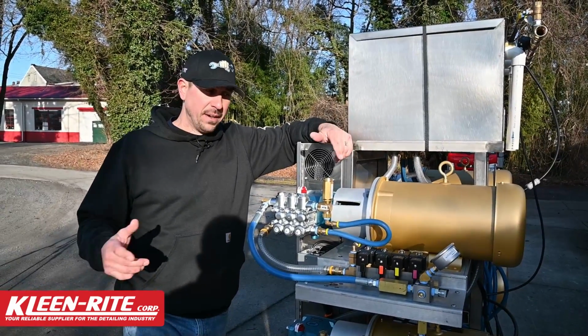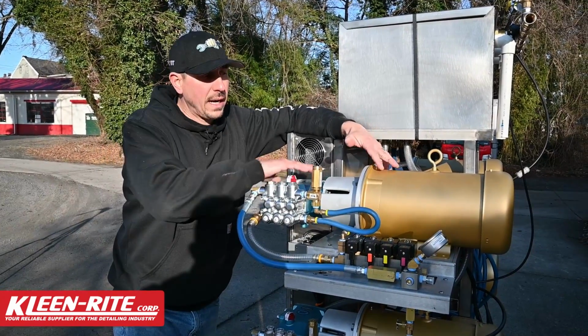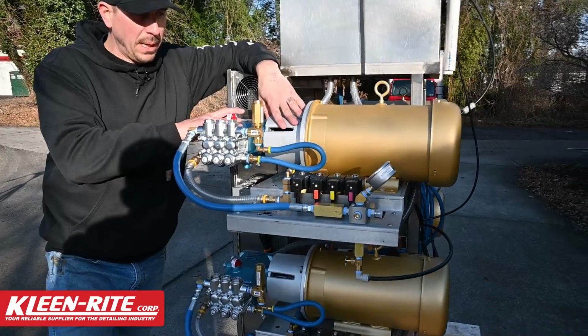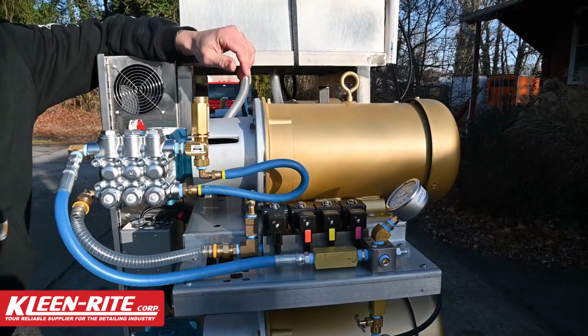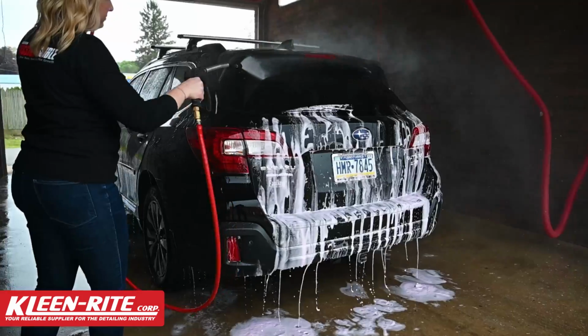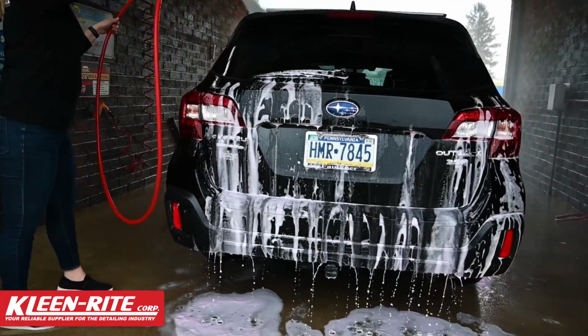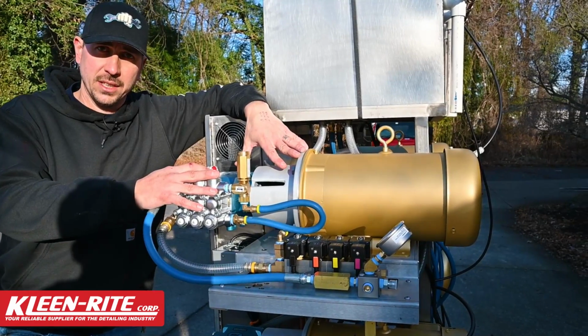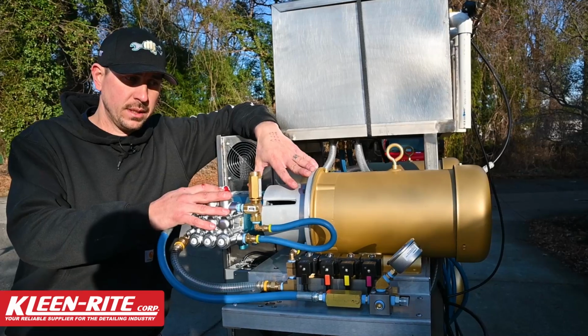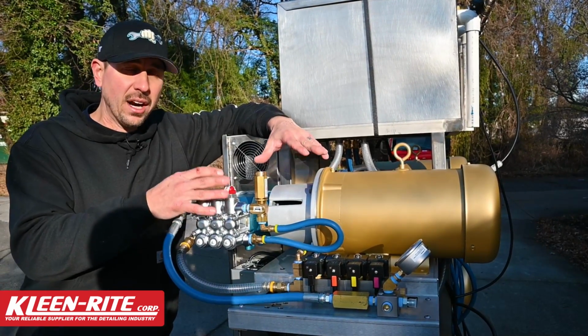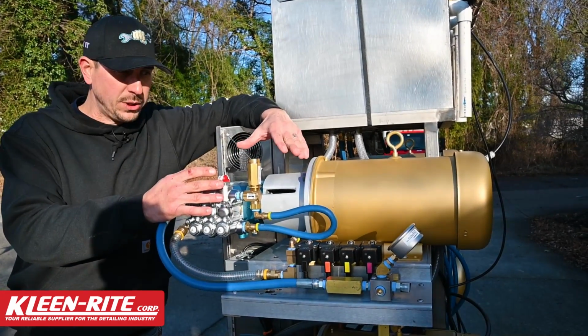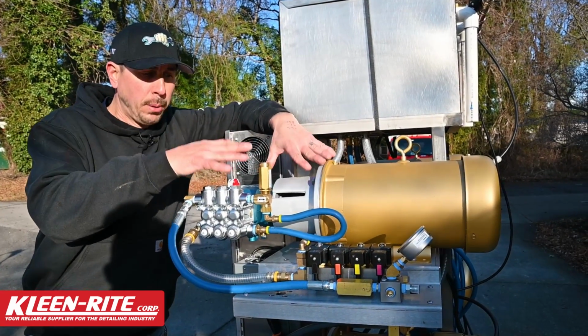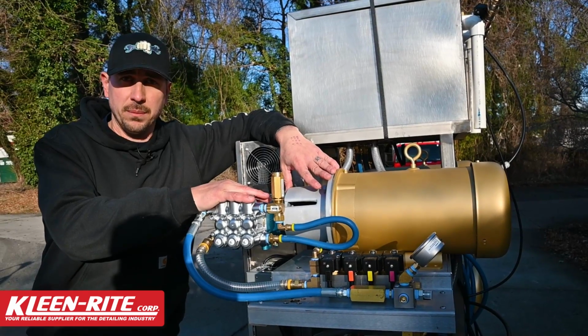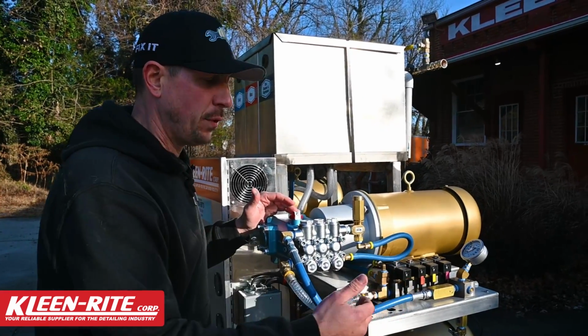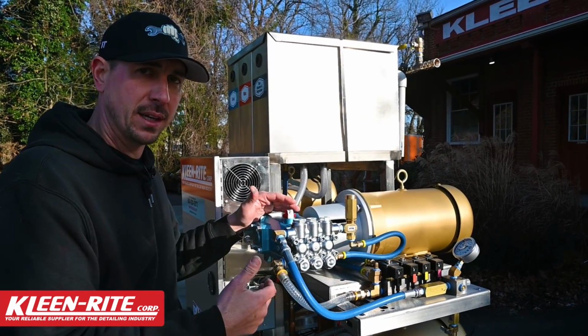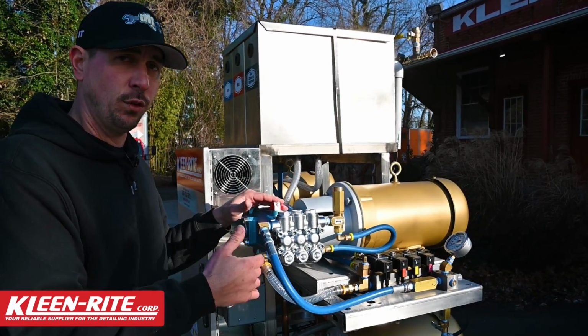So along with the VFD benefits on ease on the motor, we've also gone with a direct coupled pump to motor application. It's a bell housing coupling, and what that's going to do for us is eliminate belts, eliminate pulleys, and eliminate a lot of friction and noise. Using this setup gives us a much smoother, quieter operation inside the equipment room, and we all know how noisy an equipment room can be. The other thing that the VFD does is cuts down on air consumption. We no longer need air to drive a flojet to push a product. We can now just push that product with our VFD driven pump set. So each pump has its own reverse manifold, and we're using a reverse manifold because we are gravity feeding our product, our liquid, to the pump head to ensure that it gets full flow all the time.